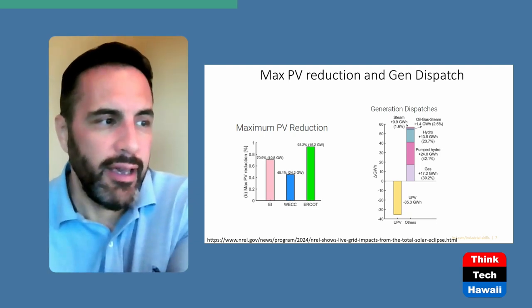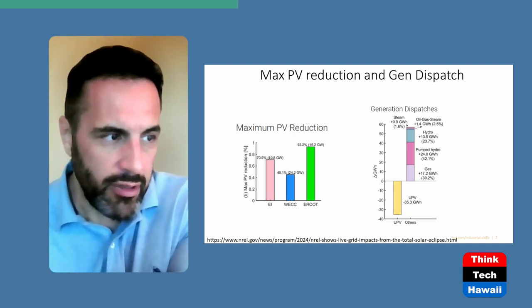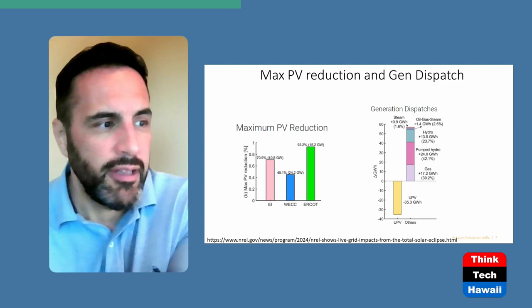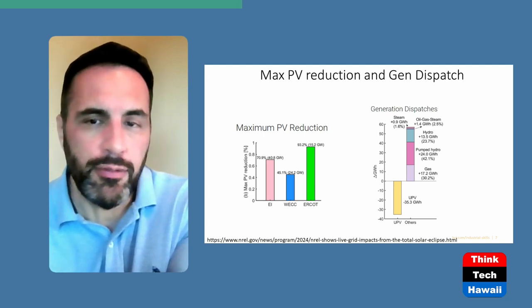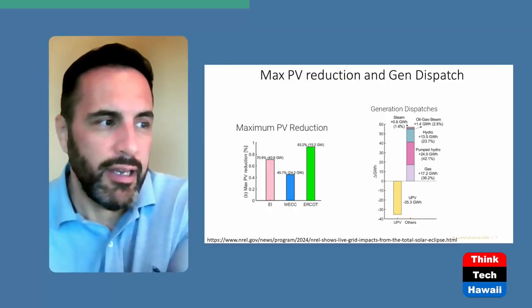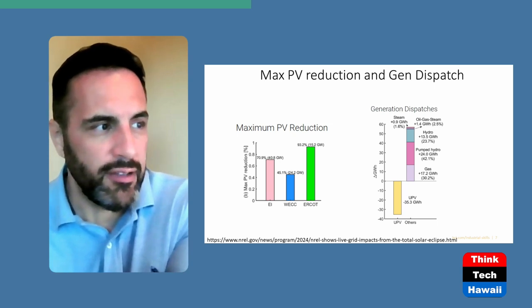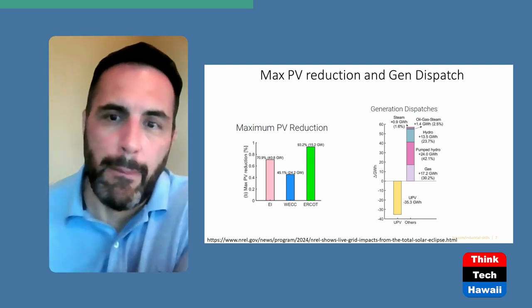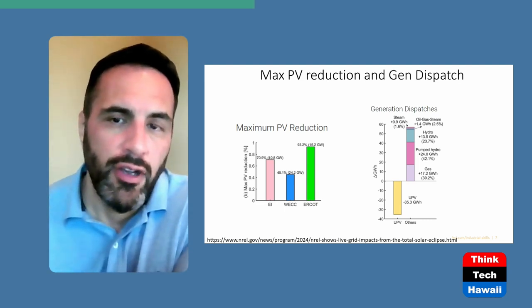To replace that generation, they ran natural gas units — about 17.2 gigawatt-hours, covering roughly 36 percent of the deficit. They ran pumped hydro — your tried-and-true battery, exchanging water between an upper and lower reservoir to generate power — contributing 24 gigawatt-hours. Hydro made up most of the rest at 13.5 gigawatt-hours, plus some steam and oil-gas steam systems. The key point is that a mixed portfolio made a big difference.